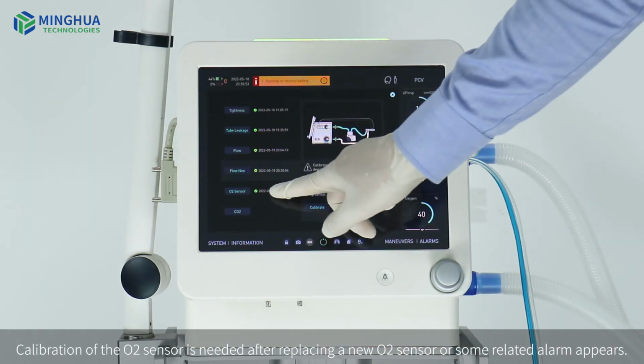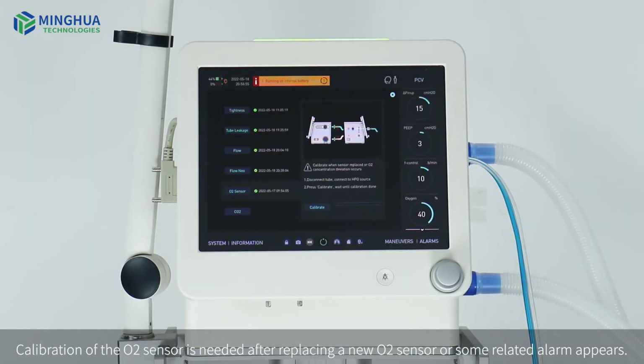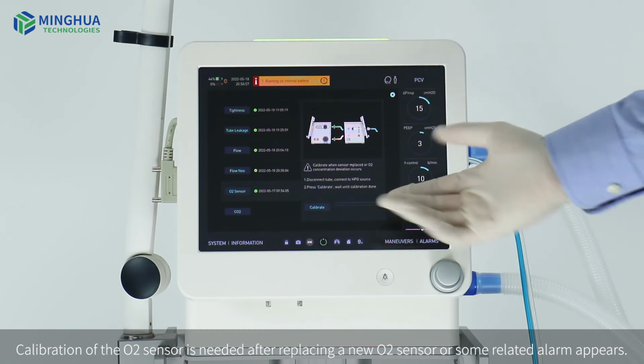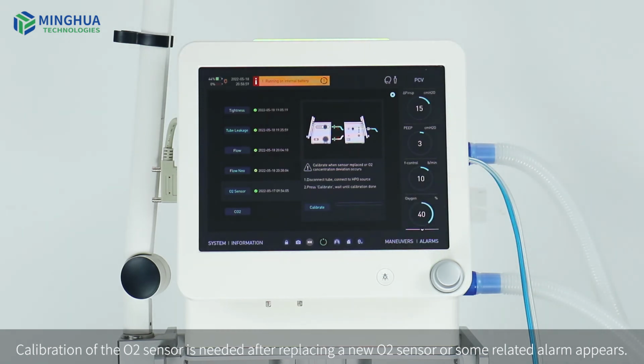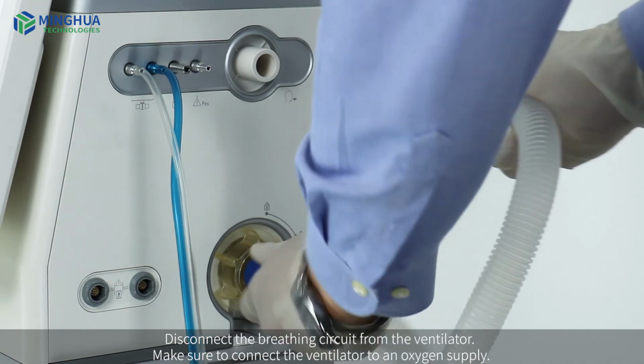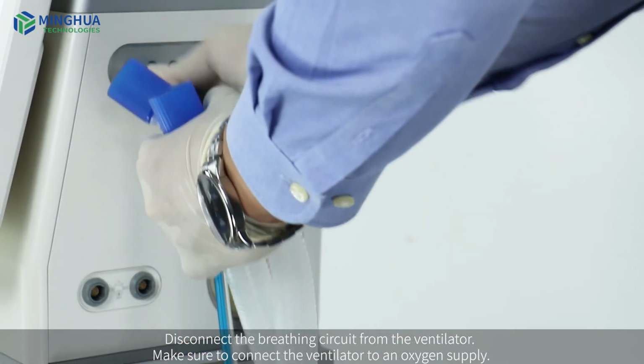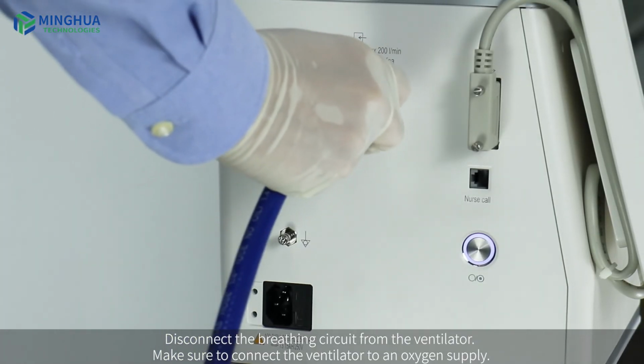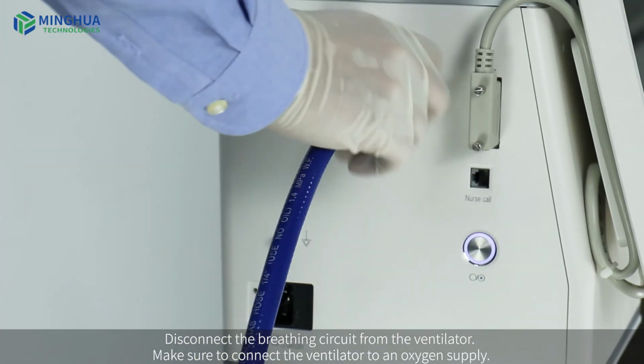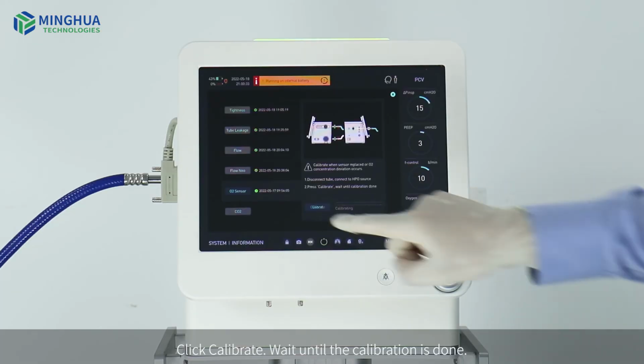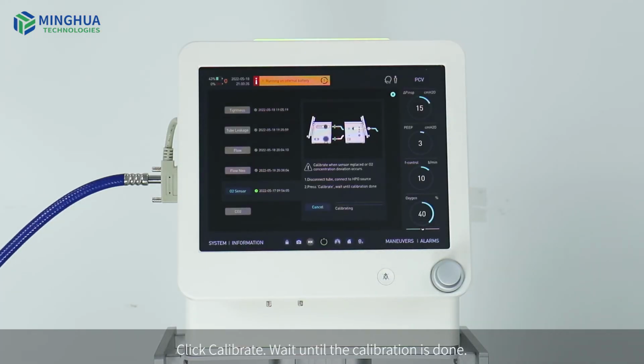Calibration of the oxygen sensor is needed after replacing a new oxygen sensor or some related alarm appears. Disconnect the breathing circuit from the ventilator. Make sure to connect the ventilator to an oxygen supply. Click Calibrate. Wait until the calibration is done.